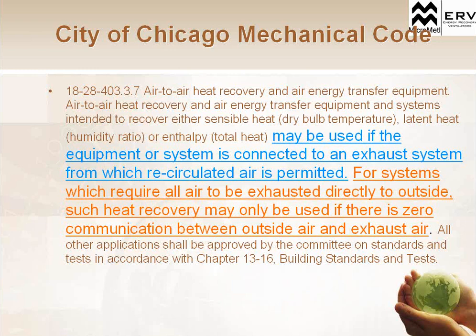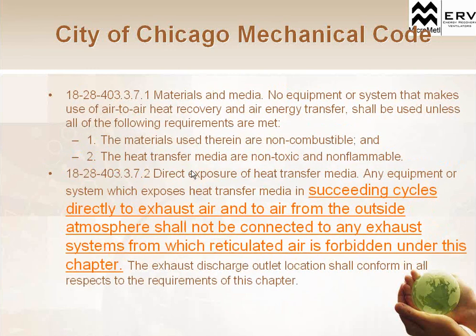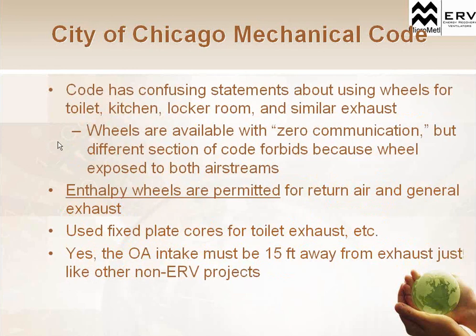We didn't talk specifically about the fixed plate heat exchangers, but a fixed plate heat exchanger would actually provide zero cross-contamination because of the airflows between the two systems. So in those applications, we use fixed plate. But there are applications where we can use a purge angle to get zero transfer, the entering air transfer ratio to zero for a lot of those wheels. So the way the code in the City of Chicago is written, so seating cycles directly exhaust air from outside the atmosphere should not be connected to any exhaust system from which recirculating air is forbidden under this chapter. So we can't use toilet exhaust in a wheel application, but we can use a fixed plate heat exchanger because it provides that zero crossover ratio.